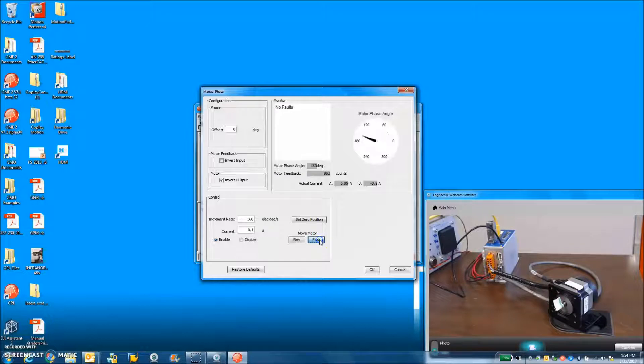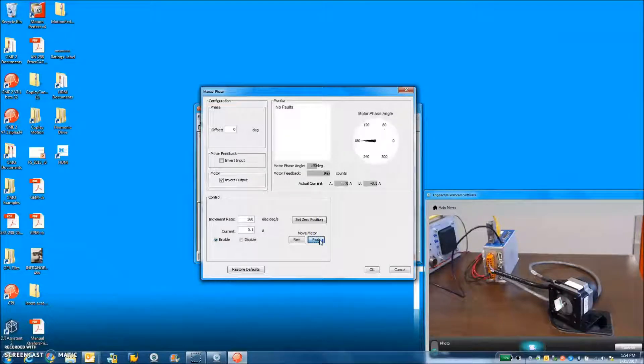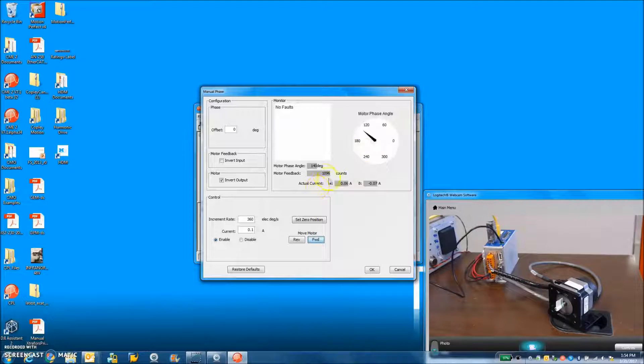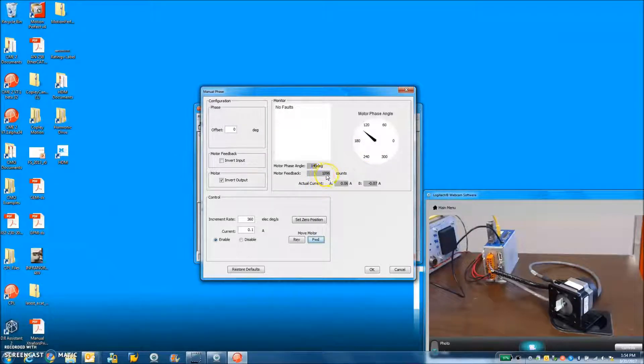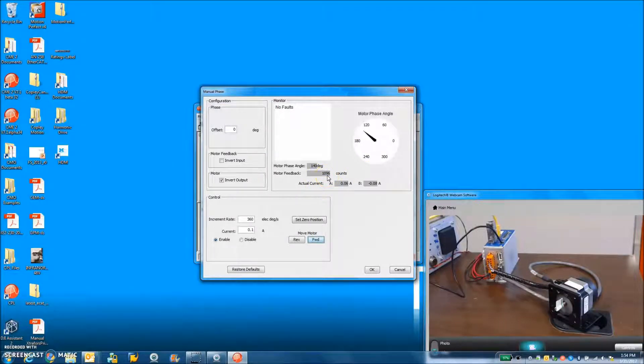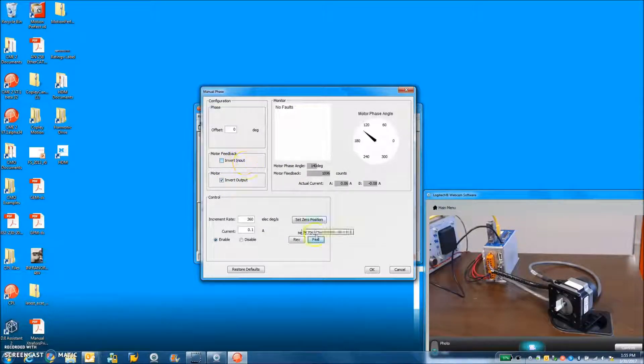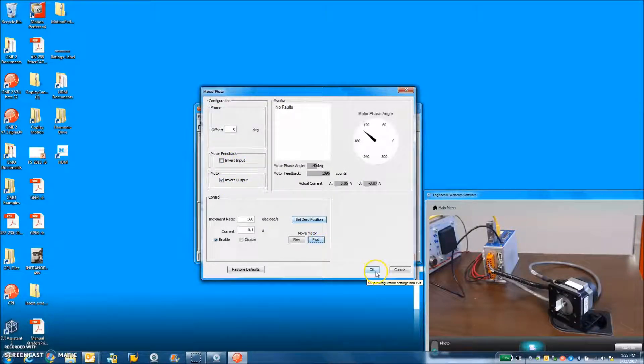You can see the motor shaft rotating in a clockwise direction. I like that to be forward, and you can see as it's going forward, the counts are going up. If you don't know your encoder, you can rotate the shaft in the motor one time, which is 50 electrical cycles, and you can confirm that you have 4,000 counts per rev. If you don't like the motor direction, you can invert it and then invert the encoder direction. When you go forward, counts go up.